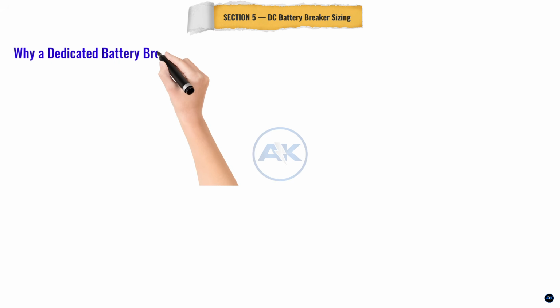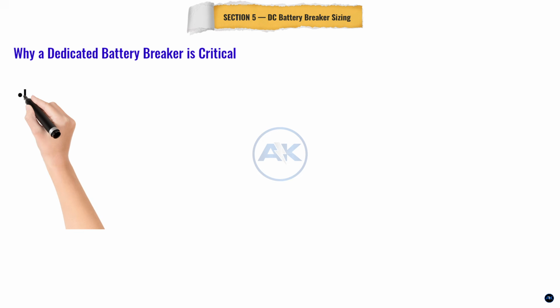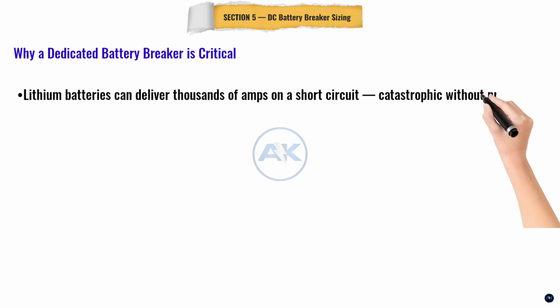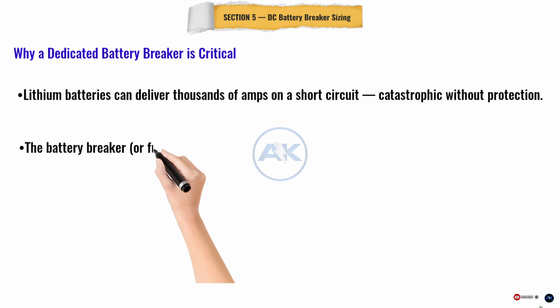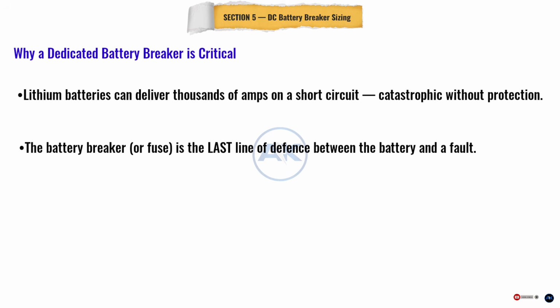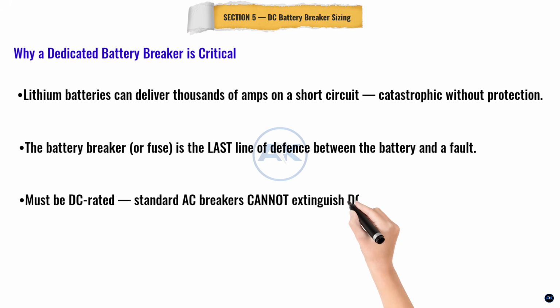Section 5C, DC battery breaker sizing. This is the most important protection component in the entire system, the DC battery breaker. A lithium battery can deliver thousands of amps into a short circuit. Without proper protection, that means fire, explosion, or destroyed equipment. The battery breaker must be DC rated. I cannot stress this enough. A standard AC breaker cannot safely interrupt DC current. It will arc, weld shut, and fail.